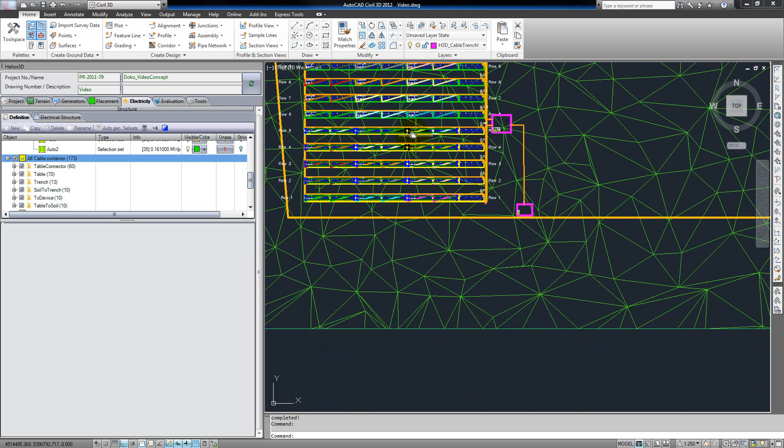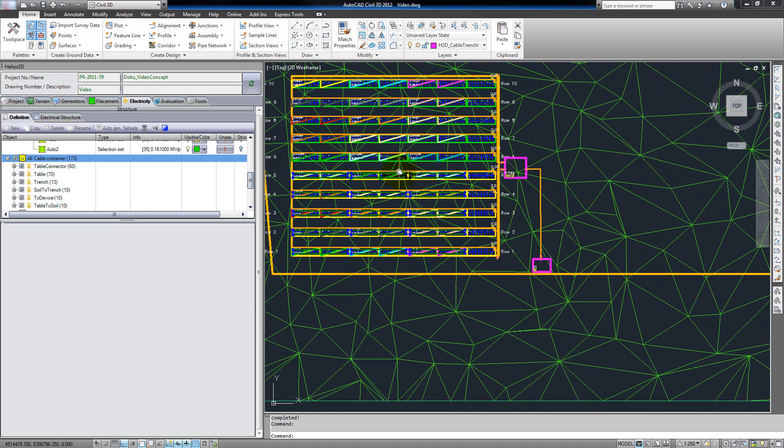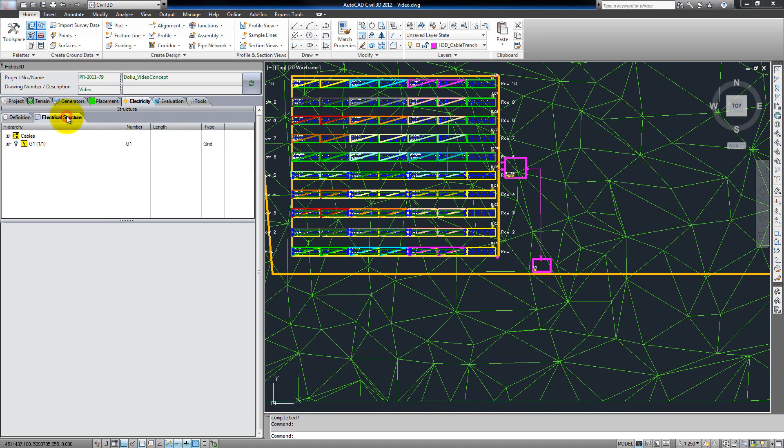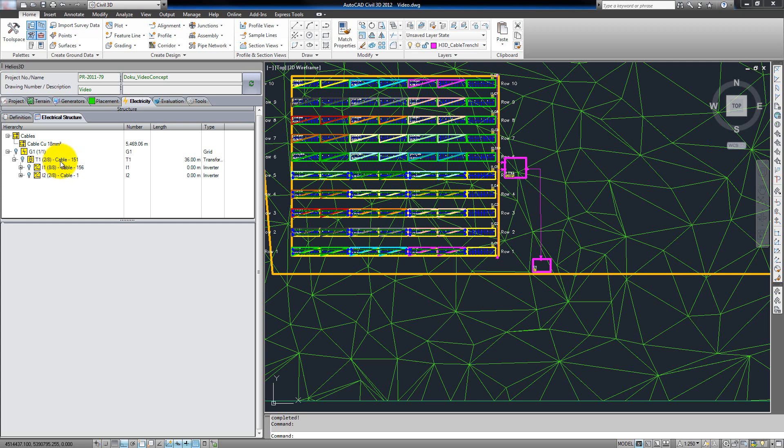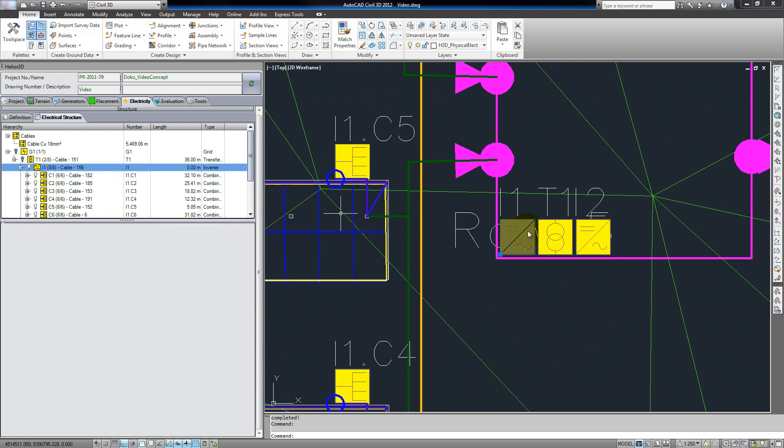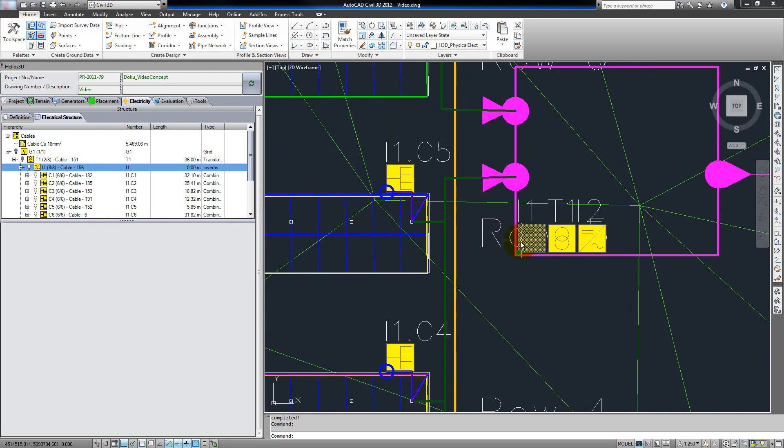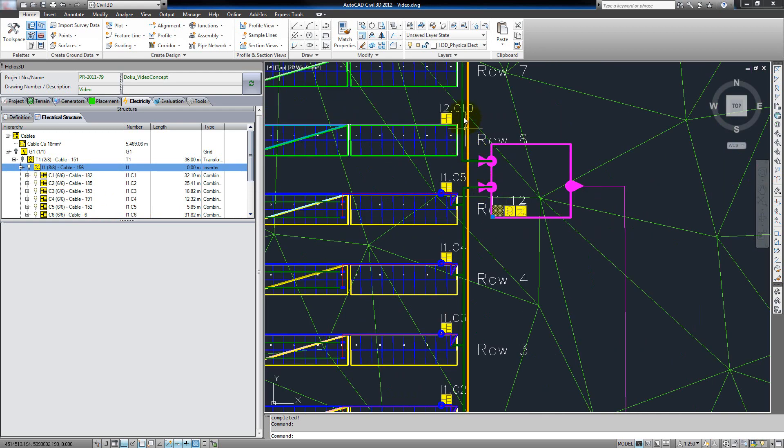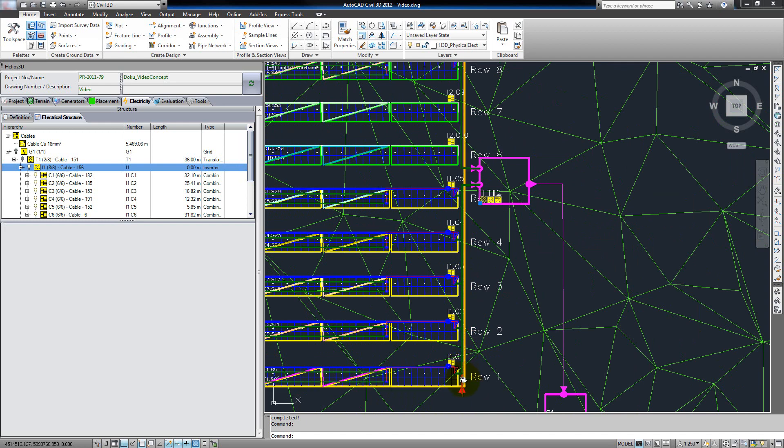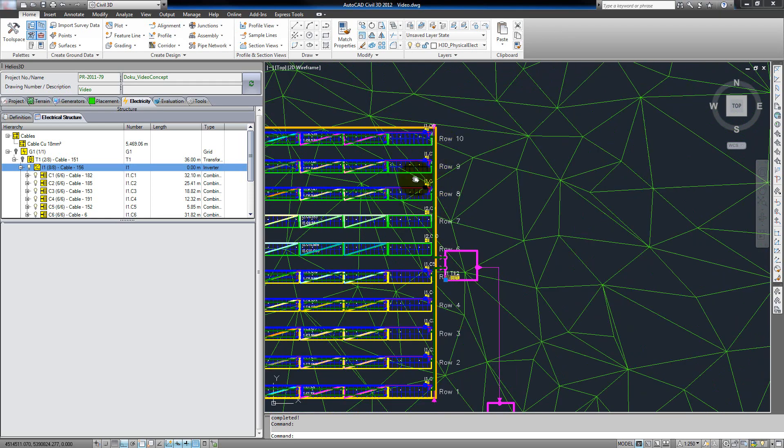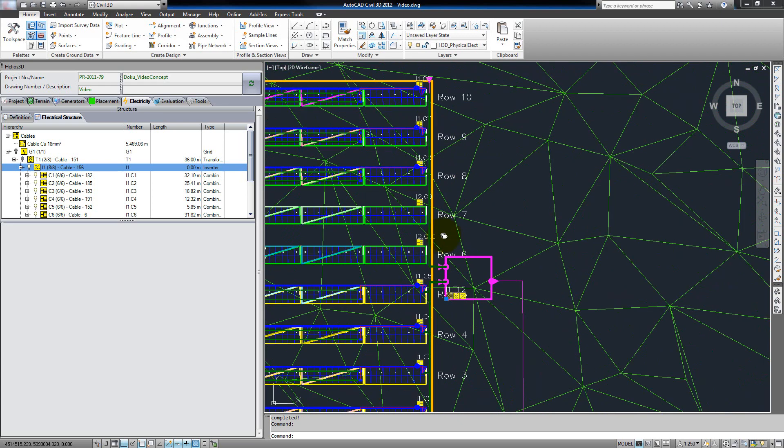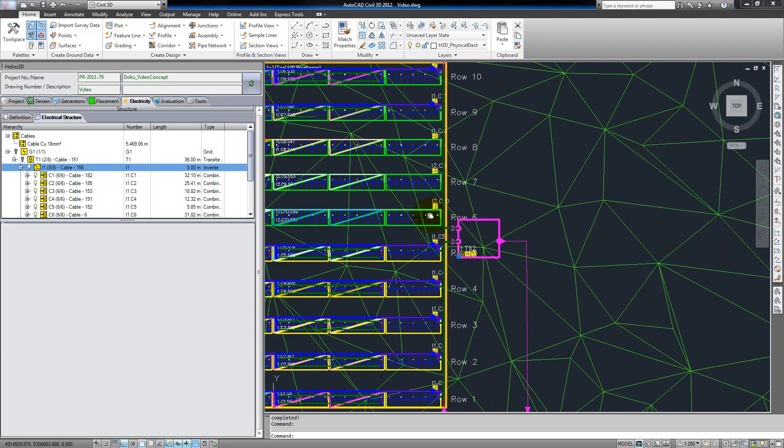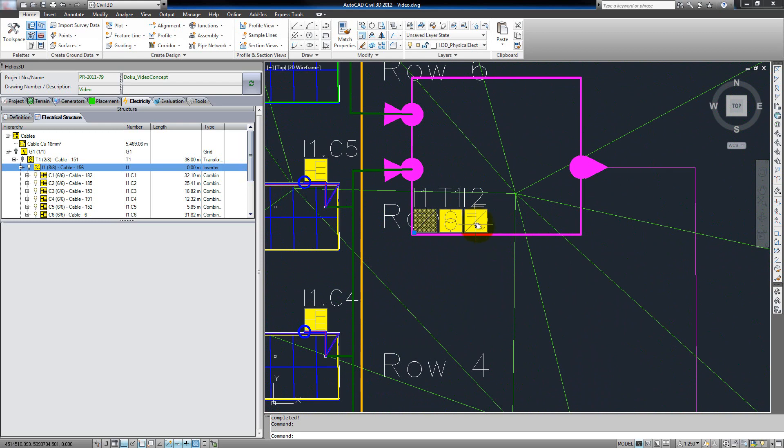Another possibility for looking at the results would be switching these off and going to the electrical structure tab. Here again we can switch on and off some layers, but this time it's connected to special devices. For example, we can double click this inverter, so Helios automatically zooms in, and we can see the inverter here. And we can switch on the layers for the complete cabling for this inverter. That means this inverter is connected to both cable trenches. Any string on the lower selection set is connected to this inverter, and the last three rows of the upper selection set are connected too. All strings of the other two rows are connected to the second inverter.